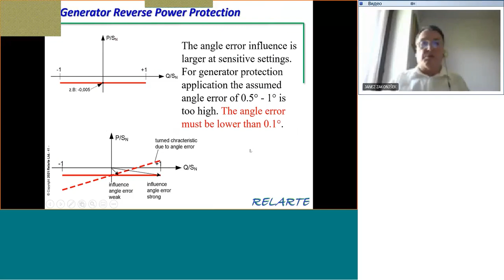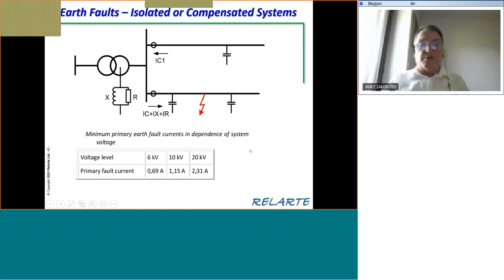Or, for example, which is also very typical for Russia, you have isolated or compensated systems, very much, even up to 110 kV, not only at the distribution level, which is here, for example. So you can see that the primary fault current is extremely low in such cases. And not only this, but it is very, very low. It is also important that the angular accuracy for this very low fault current must be very good. Otherwise, you will again get wrong operation of earth fault protection in isolated or compensated systems.